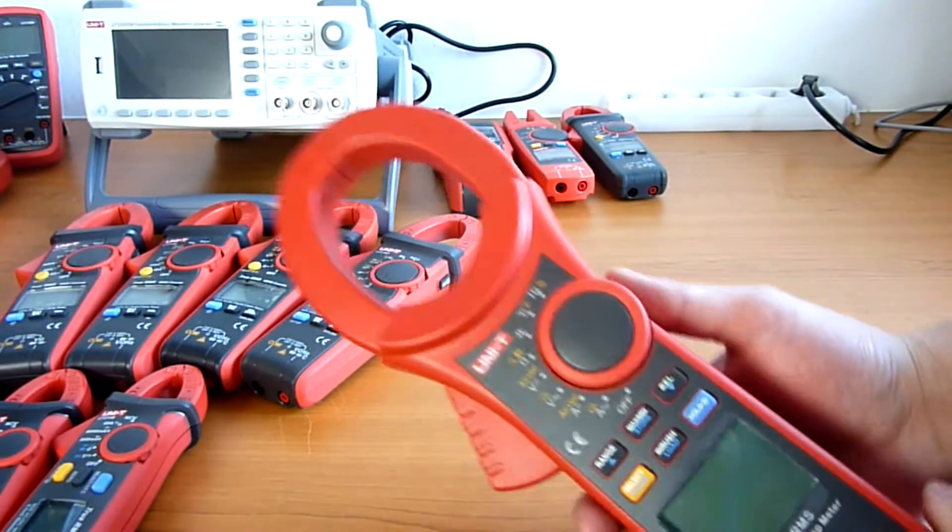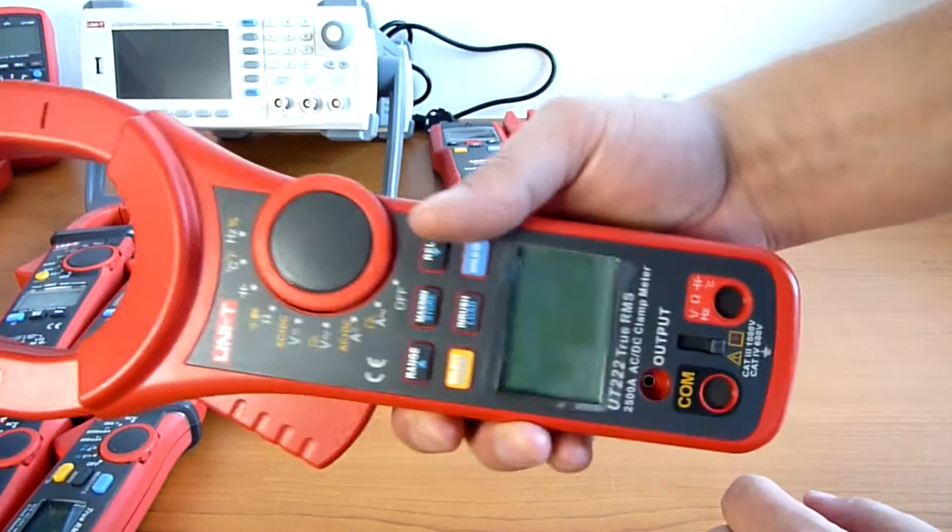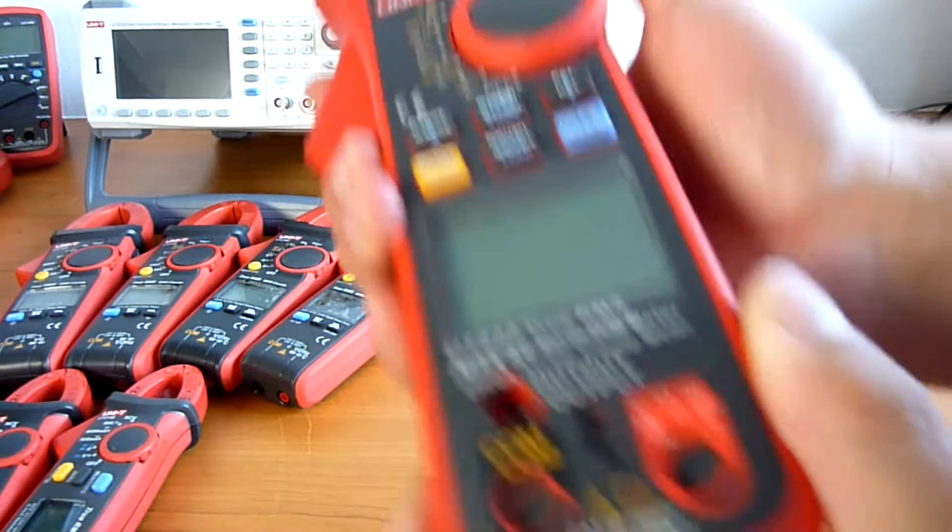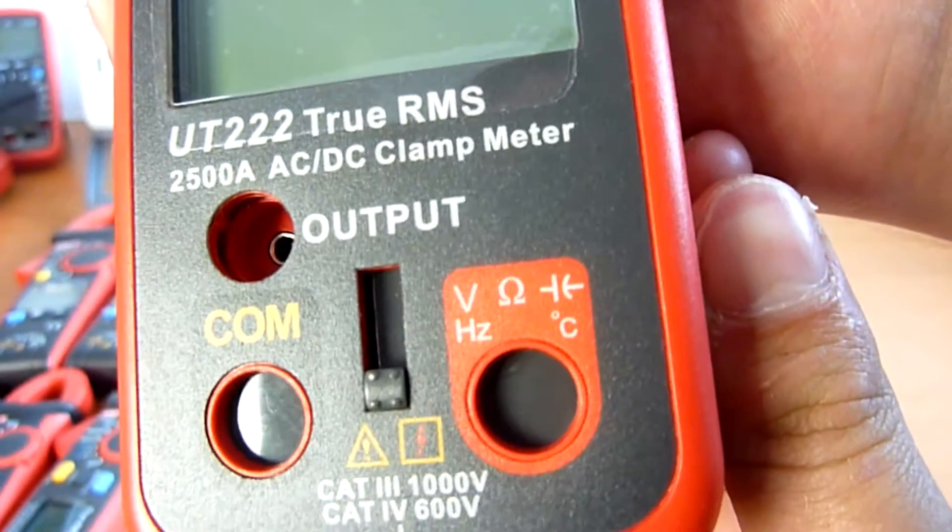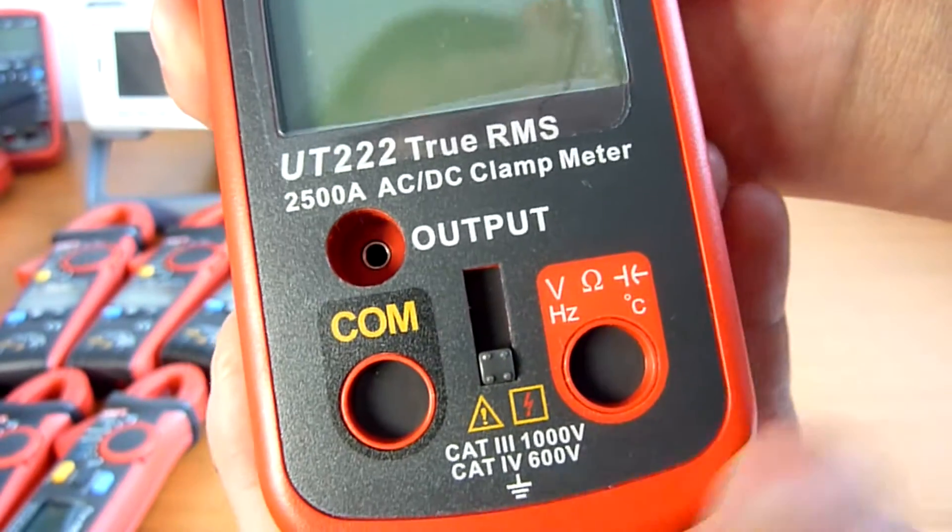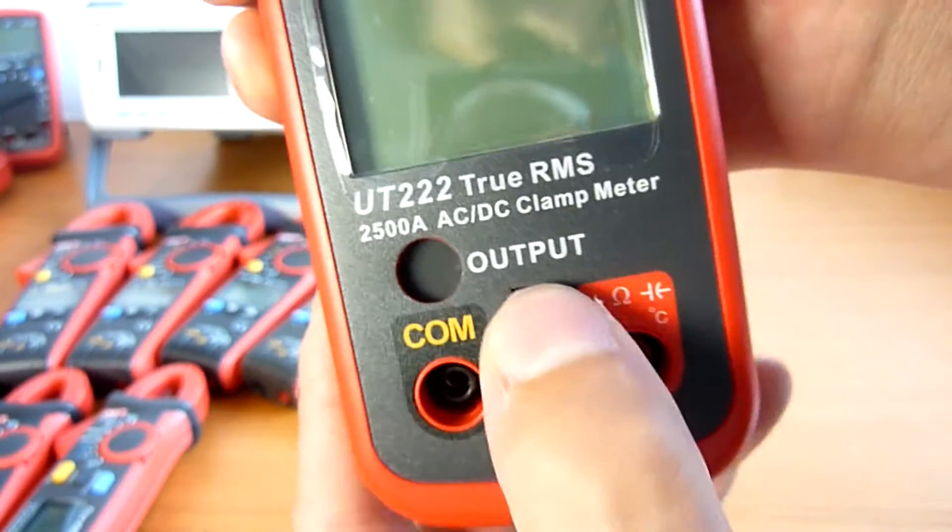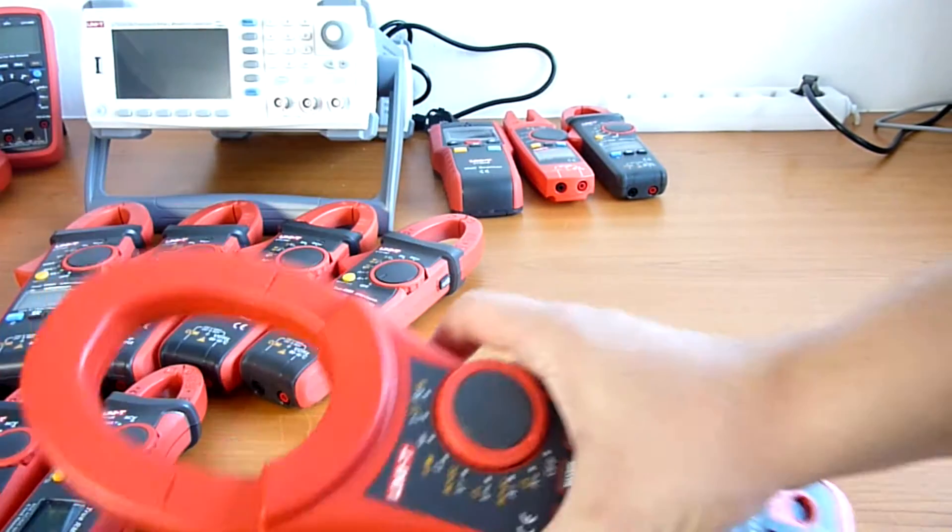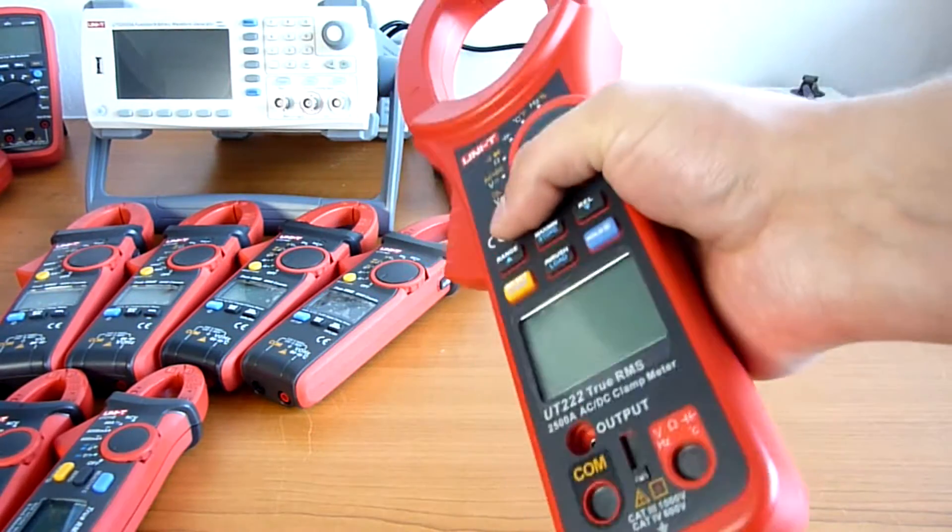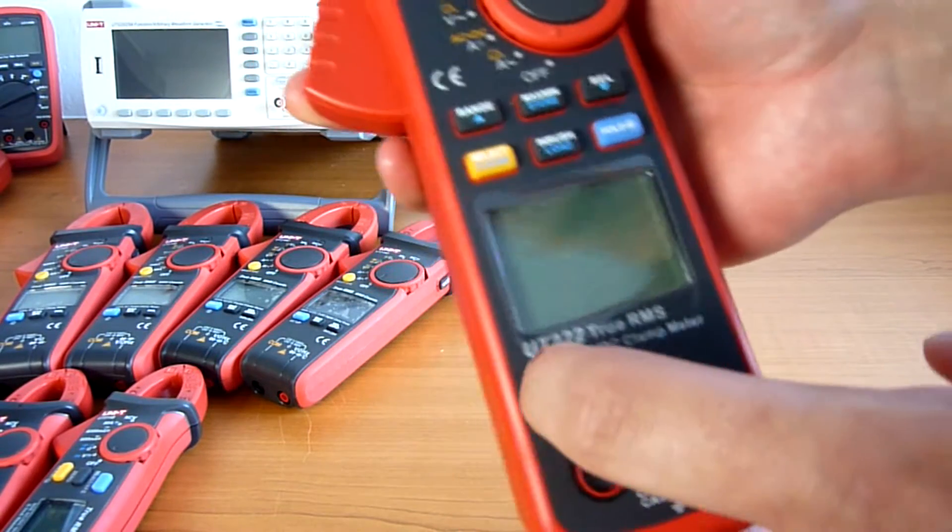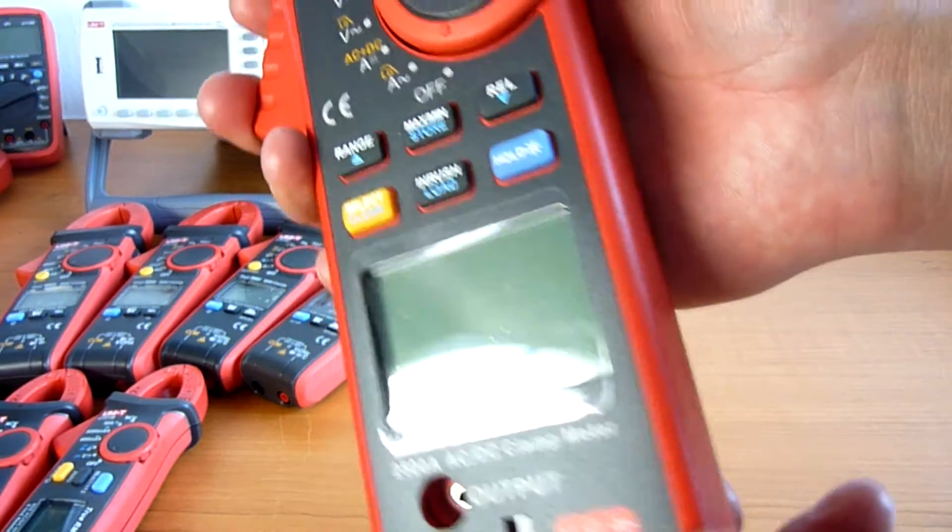Here we have an industrial high current clamp multimeter with huge clamps, currents up to 2500 amps, with a very special function. You see there is also an output and a mechanical switch. The output basically allows you to use your oscilloscope and display like 2000 amperes converted to millivolts through here. It's a very handy function.